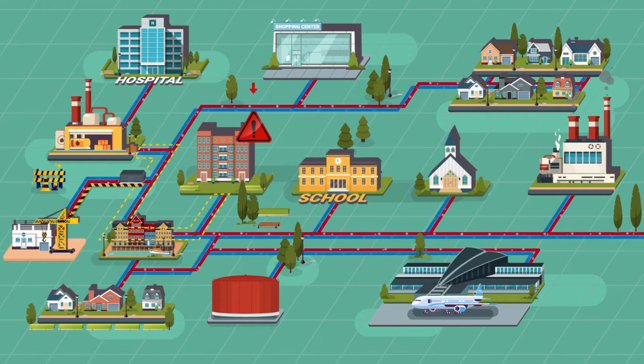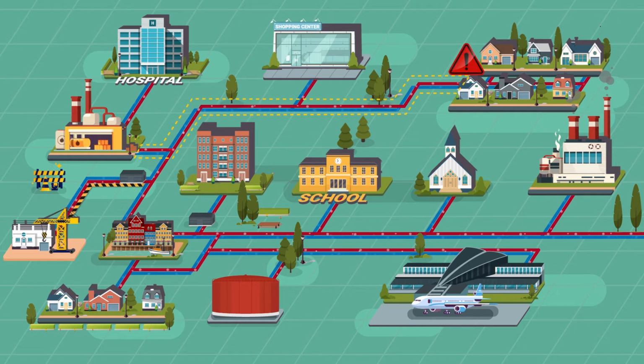For instance, here, where they are expanding the district heating network. In this case, a booster station can ensure a correct pressure all over the network without stressing the pumping system at the district heating station. At the same time, you can optimize the energy efficiency of the new parts of the district heating network, preventing as much heat loss as possible when the local pumping station ensures the correct pressure.